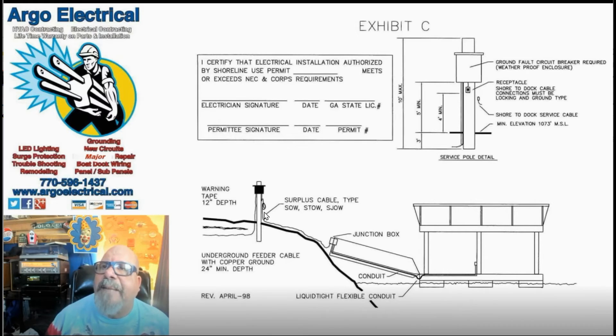You see right here they have a rolled-up cord. The cord requires you to have between 75 and 100 foot so you could release it out as the water in the lake goes down. And if it rises, obviously you'd want to reel it back up. You see SOW cord, STOW cord, and SJOW cord — that means it's waterproof.